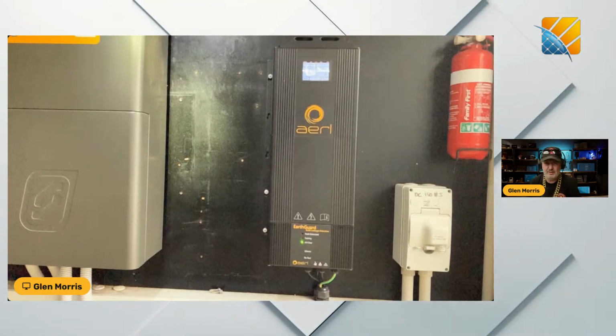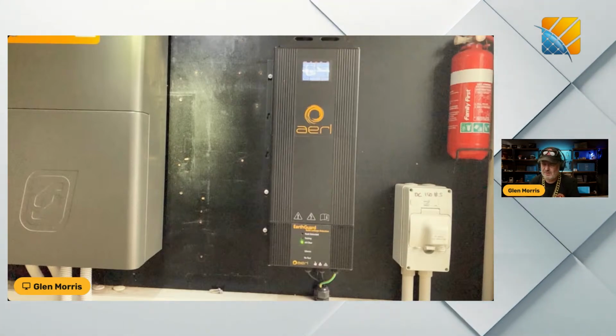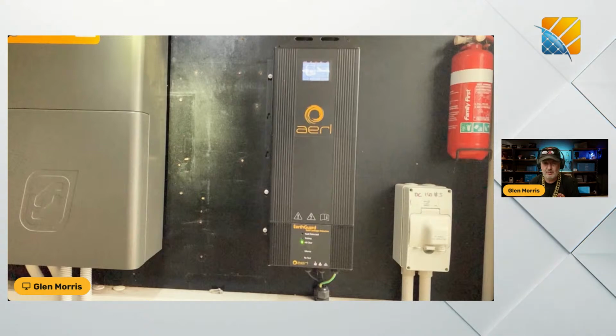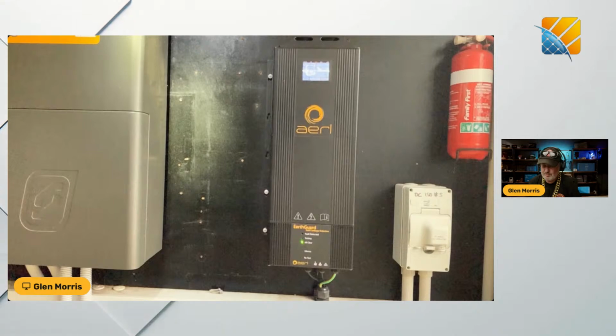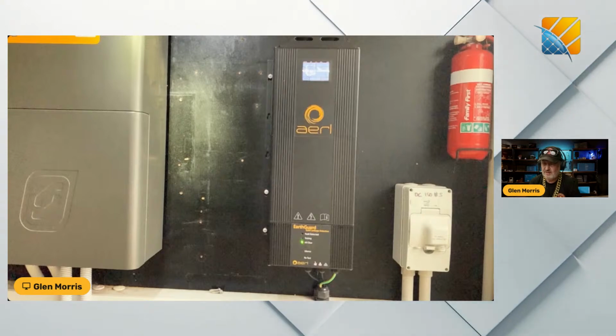They also make an Earth Guard device, on the bottom here, an earth leakage detection unit that fits onto the bottom of the MPPT, which is required under the new battery standard for anything over 60 volts. So even though we probably don't need it on this system, we've got earth fault detection on both the battery side and the PV side.